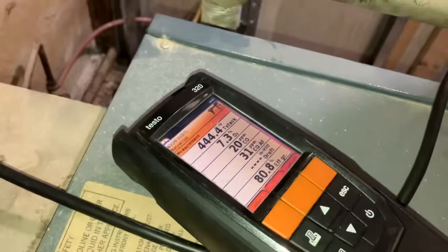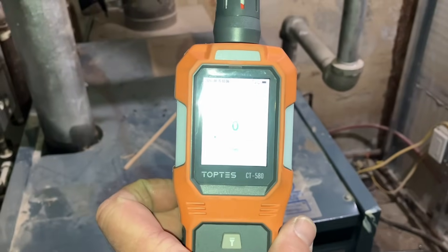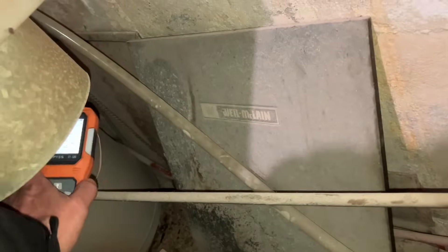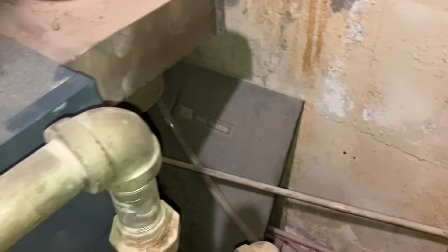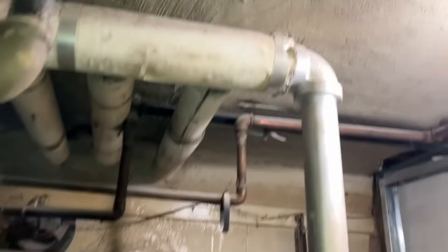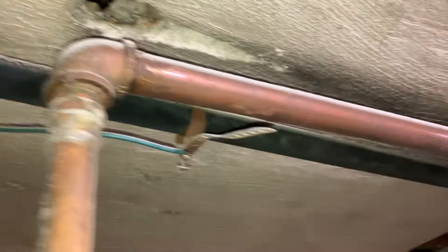All right, still good. Let's clipboard these results. The results of the combustion and draft analysis, dated with a time sticker: carbon monoxide — nothing in the house. The valve tag is on: gas for boiler, gas for water heater, water heater feed, boiler feed, service tag. I keep my hand there — no positive draft on camera either. That cover and that cover — no idea, but this is all done wrong. They didn't want to touch anything more because of all the asbestos up there. Look at that — we've even got some brass piping here in this house, from the domestic hot water line. Looks brand new, though I'm sure it's lined with scale on the inside.